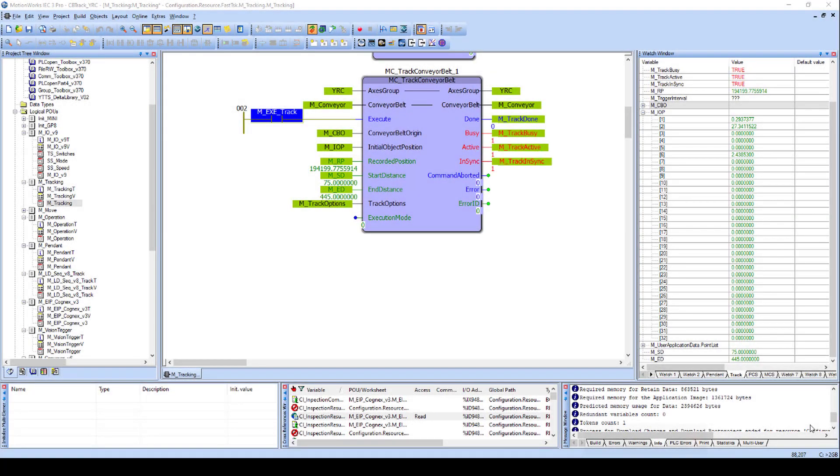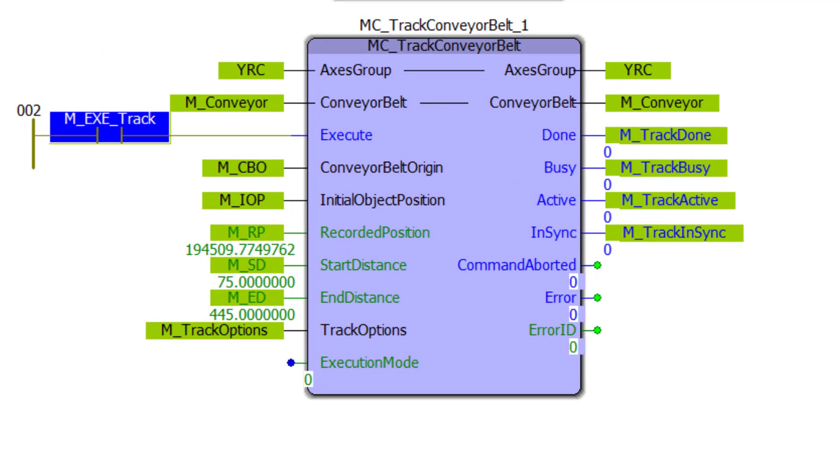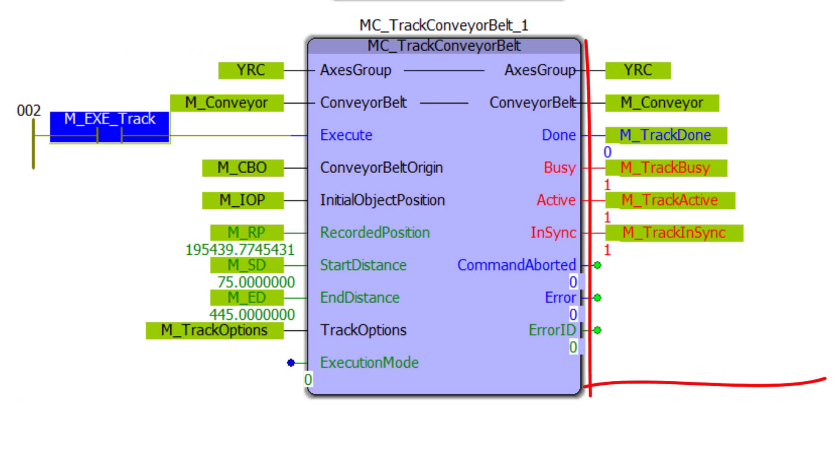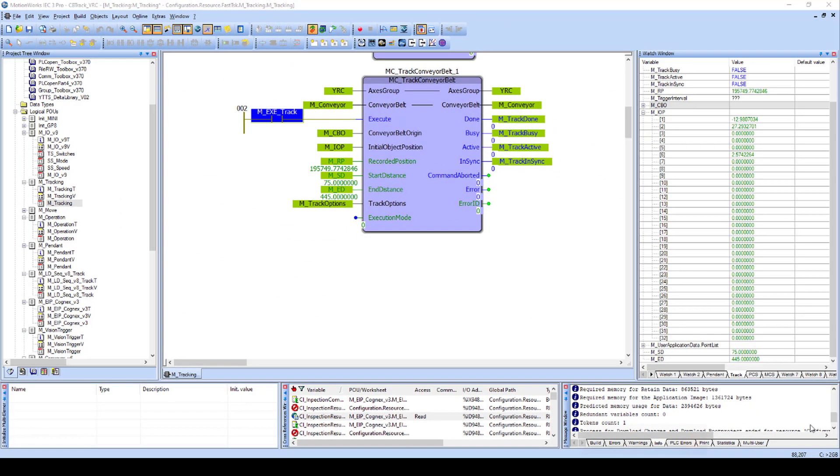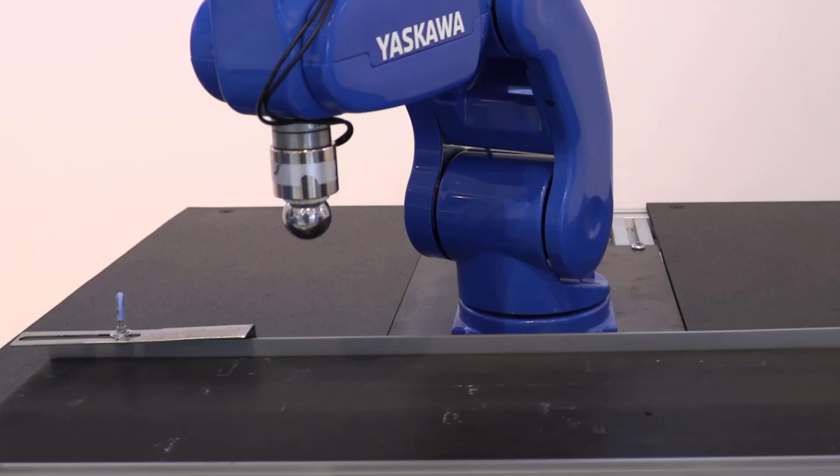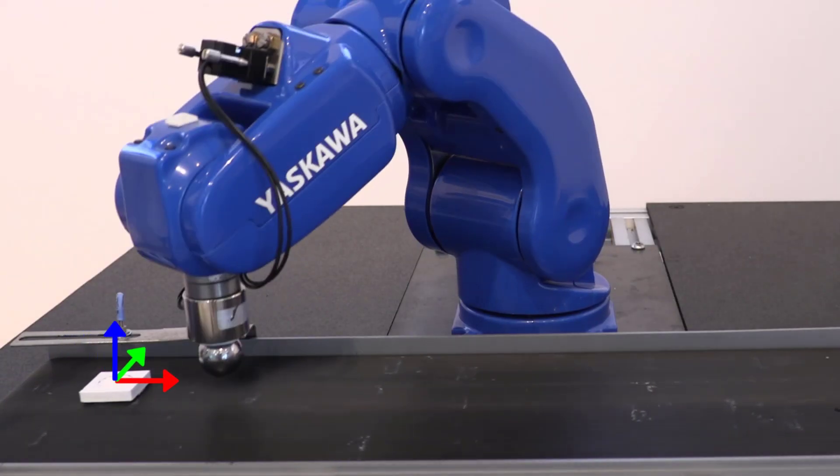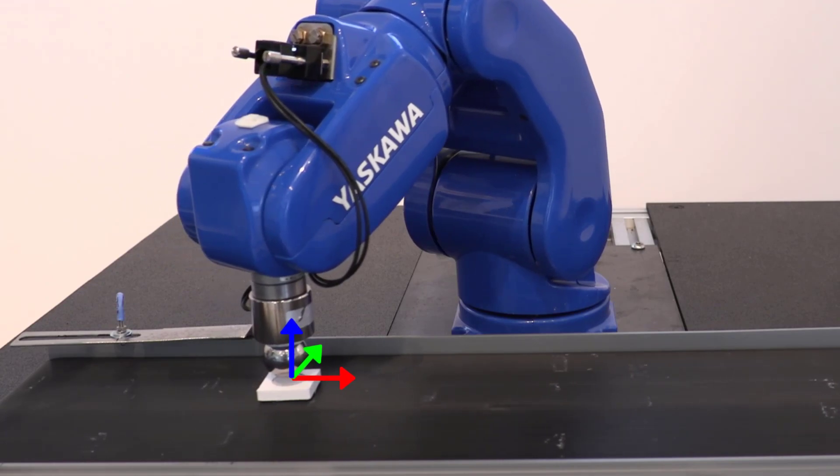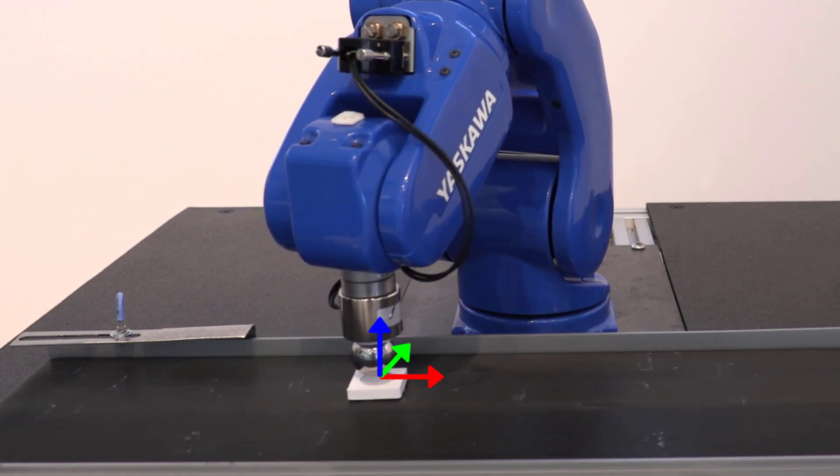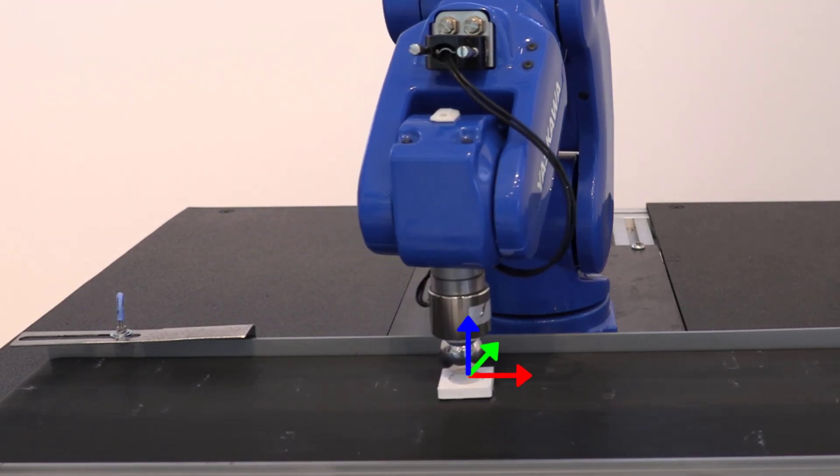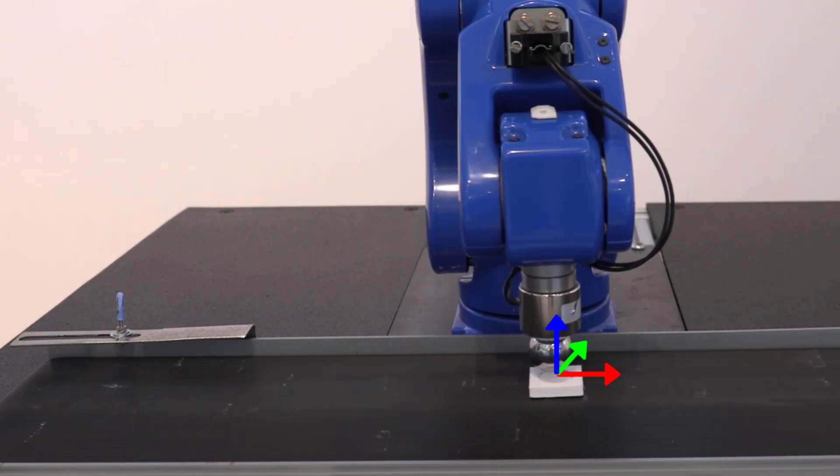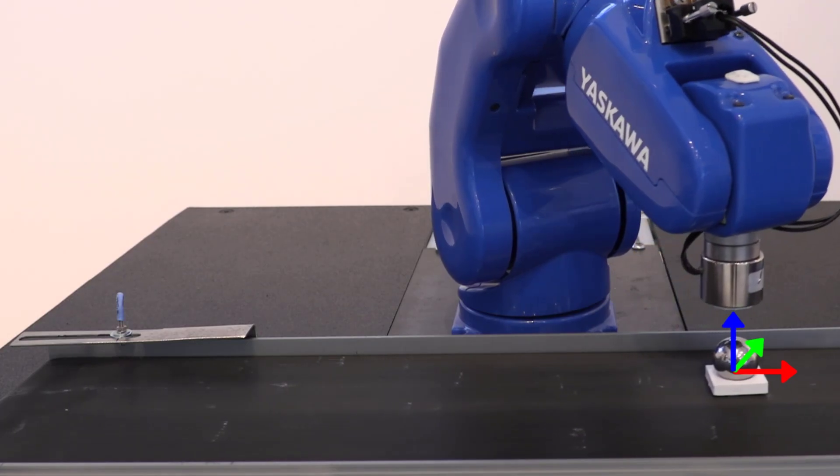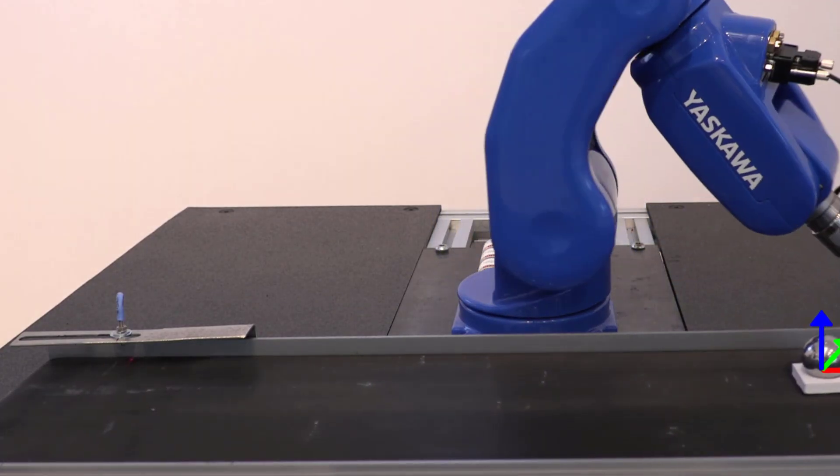The complex part of conveyor tracking is already done for you, contained in the block MCTrackConveyorBelt. The programmer provides the correct input values to the block and uses the output status to control the move sequence. Let's touch briefly on the basic principles. The most basic principle is that conveyor tracking is simply a moving part coordinate system, or PCS.